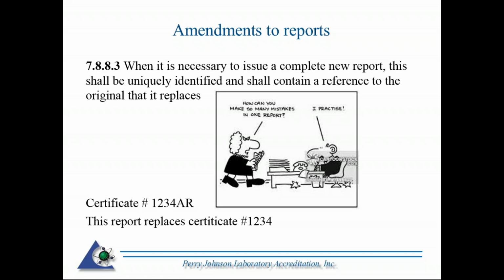You could give it a new unique identifier, certificate number 1234AR, AR being amended report. Now you need to reference the report that it replaces. So somewhere it needs to specify, so there are not two reports running around for the same sample or instrument, that this report replaces certificate number 1234.